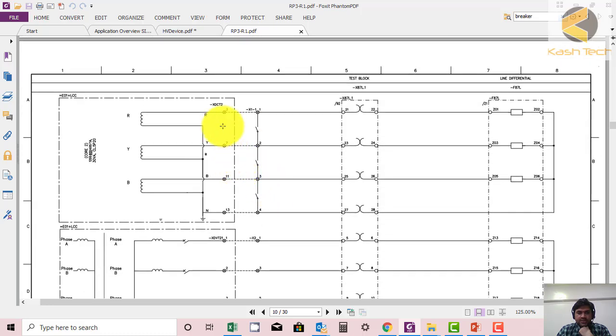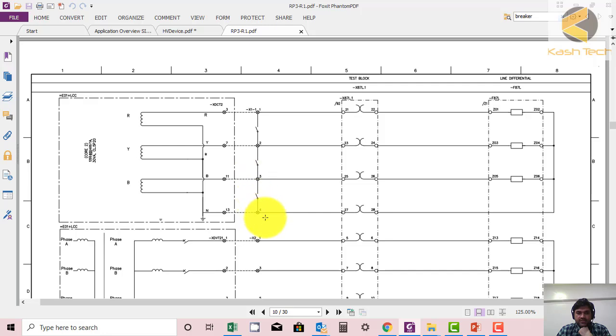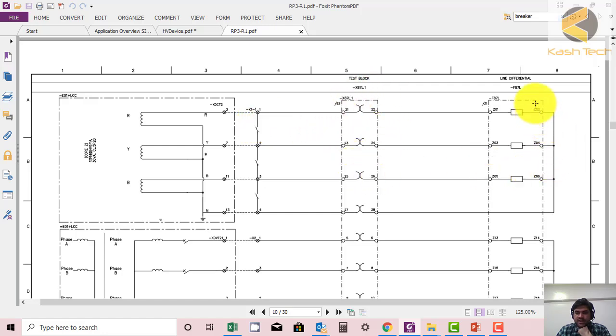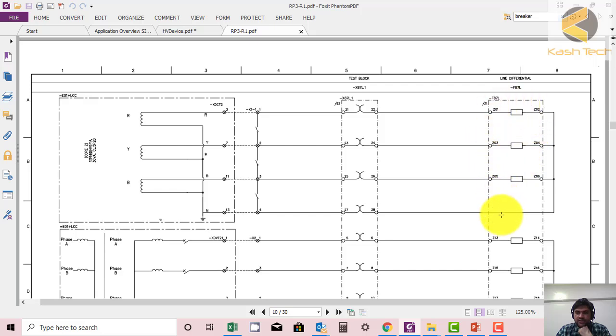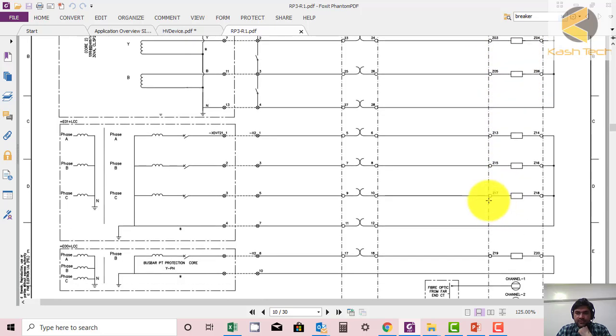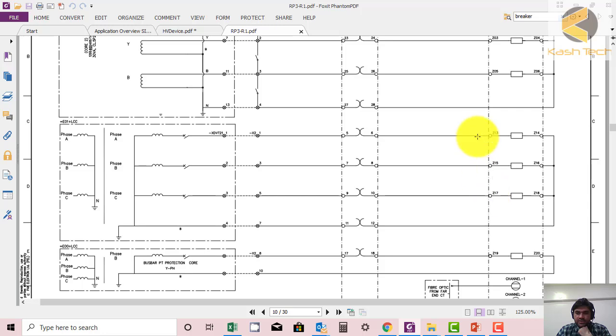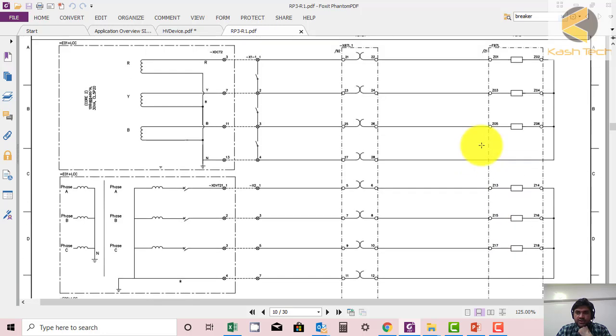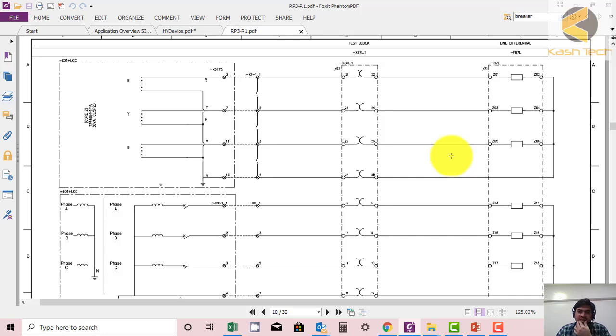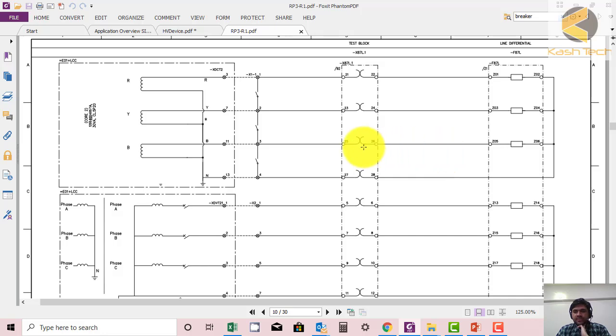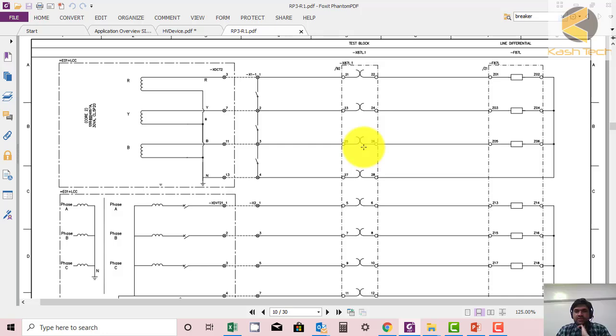This is the CT circuit coming to the shorting link. We will be discussing the CT circuit - I will tell you in detail what the function is. This is a terminal block and this is the line differential relay. Two currents are fed to this relay. Differential relay will monitor current at two ends of a feeder, transformer, or load. By Kirchhoff's current law, current in and current out should be the same. If both are different, then there is some leakage current or current is going to ground. It means there is a fault.